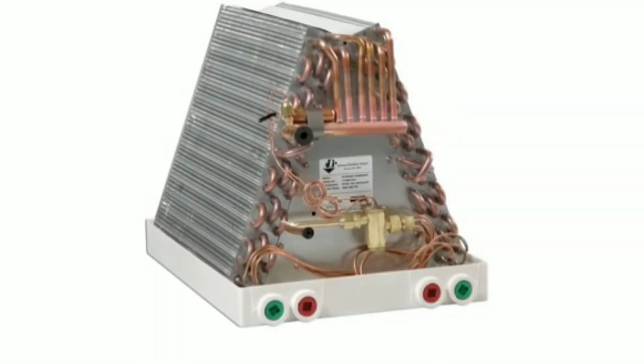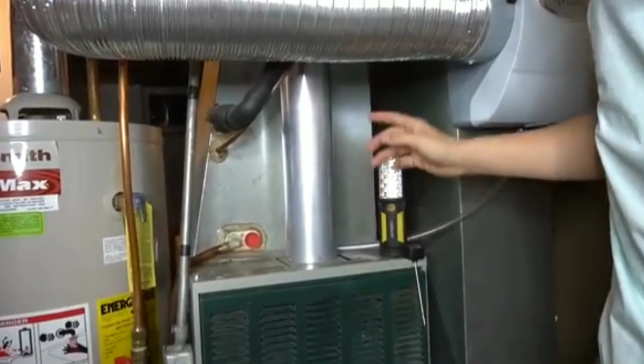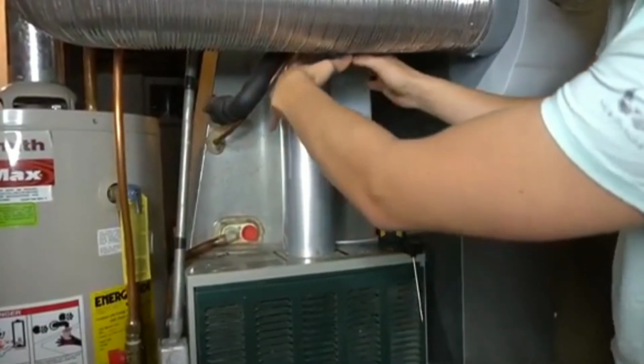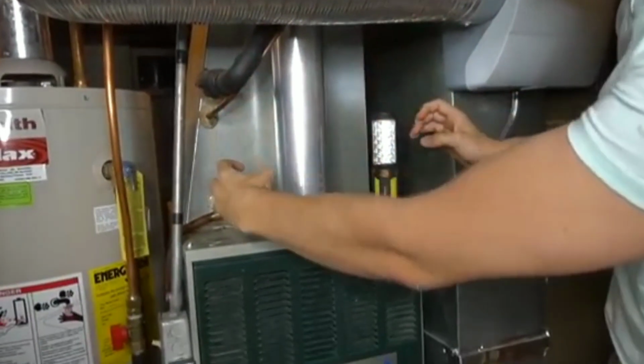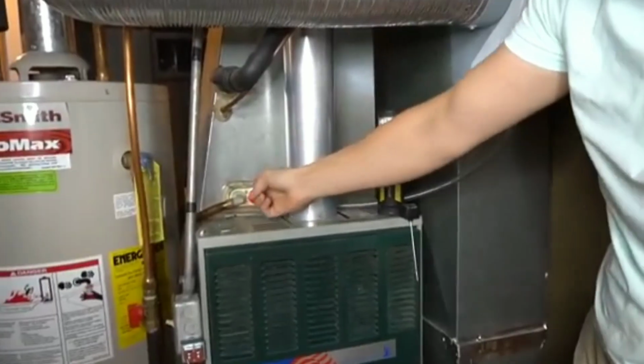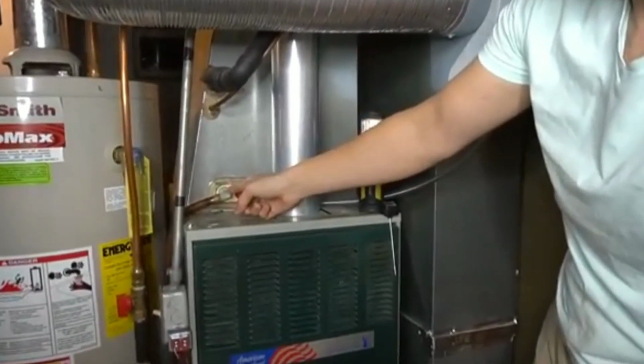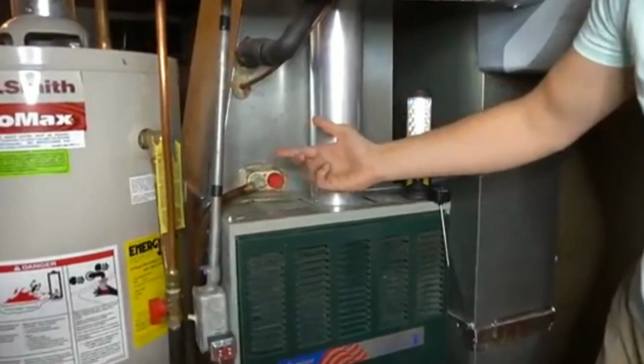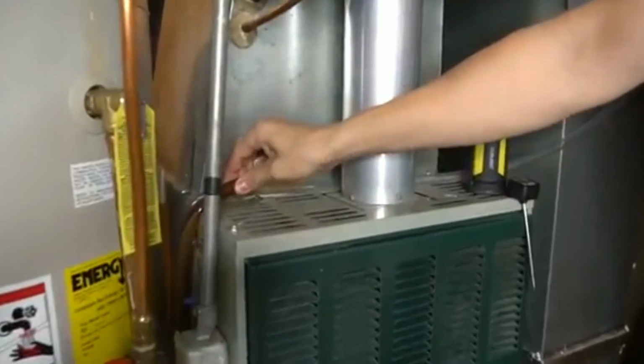And the coil, the reason it's called an A coil sometimes is because it oftentimes looks like the letter A, looks like a radiator. And that just sits on top of the furnace, and whenever it collects humidity, water kind of drains down that coil. It has a drain pan on the bottom of it, and the water comes out right through here.